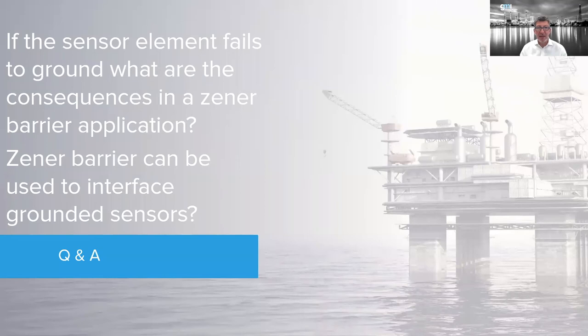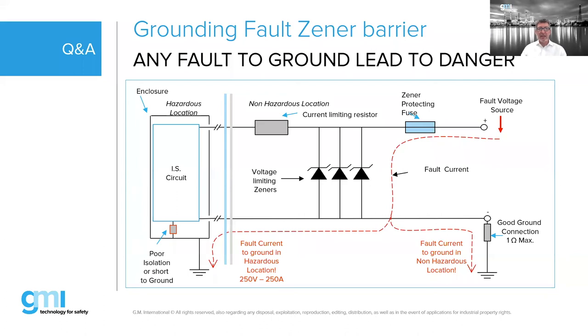If a sensor element fails to ground, can a Zener barrier interface a grounded sensor? Without a system ground, there is no safety in a Zener barrier installation. The same issue applies if you have a non-isolated sensor or if the sensor fails to ground — like a thermocouple in a thin metal casing where vibration can cause the thermocouple to touch the casing, creating a grounded thermocouple. A grounded thermocouple is a dangerous situation for a Zener barrier because the fault can be diverted to ground inside the hazardous area without any limiting resistor or diode.